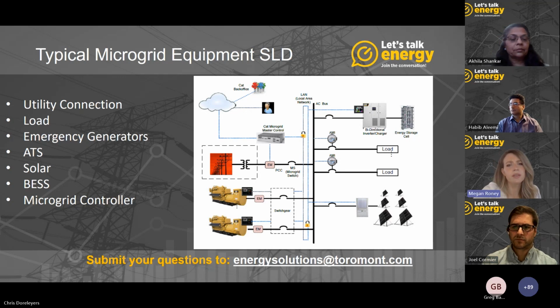Great. Thanks, Joel. Do utilities allow this type of equipment to be connected to their grid? Great question, Megan. So I would say one of the first steps that should be done by a customer or a consultant when exploring the opportunity of implementing a hybrid energy system would be to contact their local utility authority and complete an application to determine whether or not you are allowed to connect the additional power generation systems to the grid. This process would provide any specific rules or limitation requirements that you would have to follow. And this type of information is extremely important for Toromont to know and understand prior to being able to suggest any solutions. So if we want to go to the next slide, please.